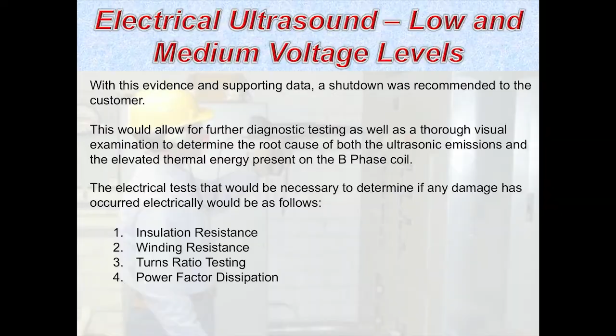And the last one here is called a power factor or dissipation factor. That's just a measure of the watt loss through the insulating systems on higher voltages between the resistive and reactive power elements. So these are measures that can be done to tell us how healthy this unit is. And knowing that things like we just heard can cause problems, it's an important thing to know.